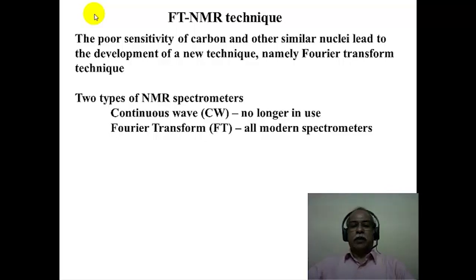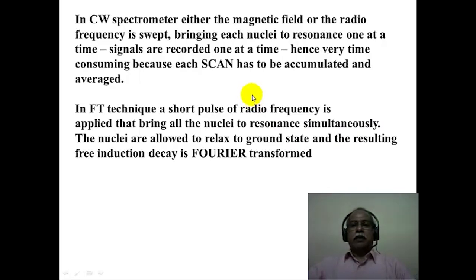There are two types of NMR spectrometers: continuous wave NMR and Fourier transform NMR. Continuous wave NMR is no longer in use — it was the original development. All modern spectrometers are Fourier transform NMR spectrometers. In the continuous wave NMR spectrometer, the magnetic field is scanned while the radio frequency is kept constant, bringing each nucleus to resonance one at a time. For example, 60 MHz NMR means the operating frequency is 60 MHz and the magnetic field strength is varied over the spectral scan width.